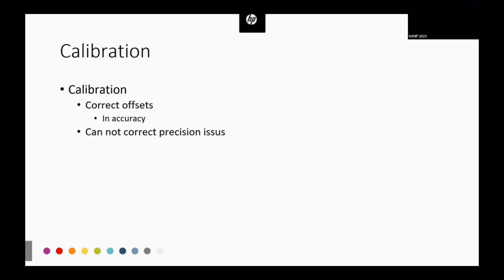When we get sensors, we can do a calibration, and calibration can correct offsets in accuracy. It's not going to change your precision. If you have a scattering of points, you're still going to have a scattering of points, it's just going to be more accurate, closer to that value. You cannot correct precision issues.